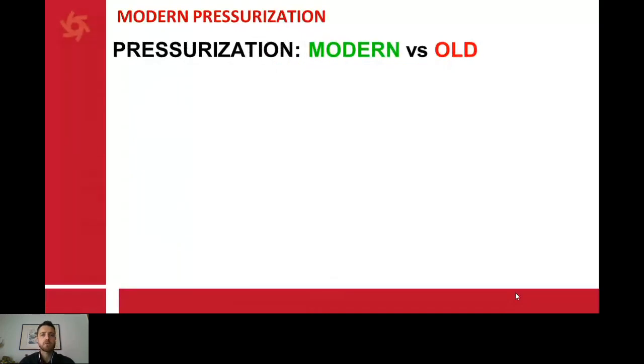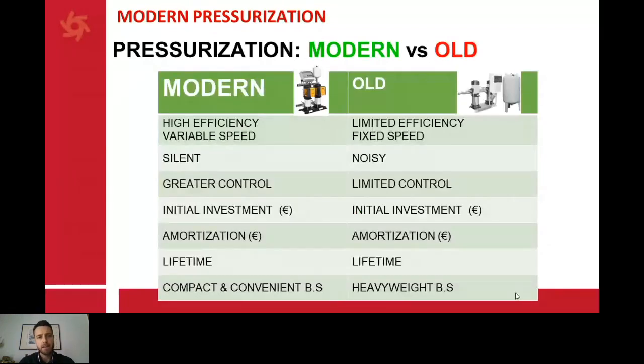Let's talk now about pressurization. Which are the differences between modern and old systems? Modern systems are highly efficient with variable speed. Meanwhile, the old ones have limited efficiency with fixed speed. Modern ones are silent, the old ones are noisy because they always run at the same fixed speed. The modern ones have great control, while the old ones have limited control. Also, there is the initial investment. Of course, the modern one is a little bit more expensive than an old one, because you have the frequency drive.